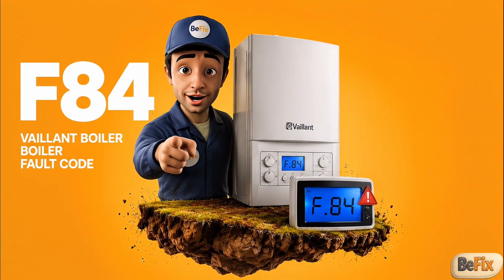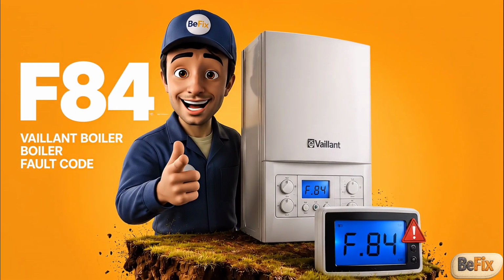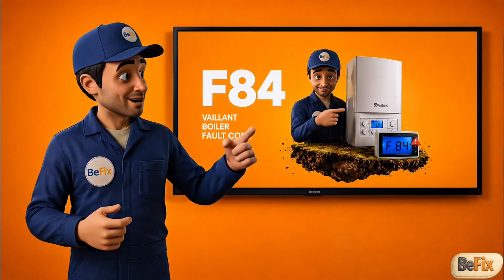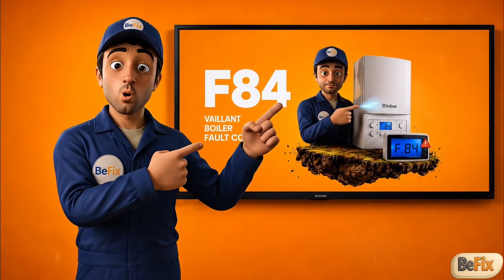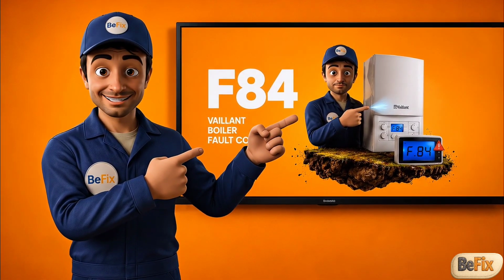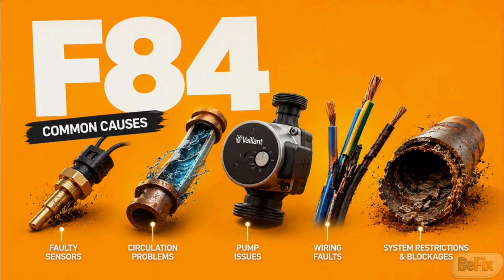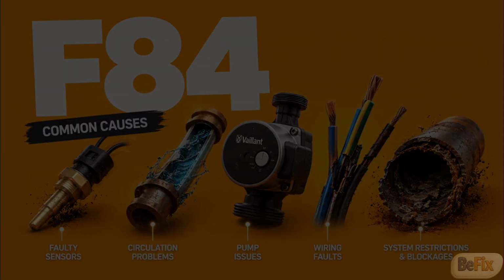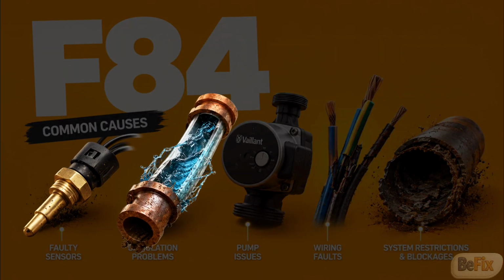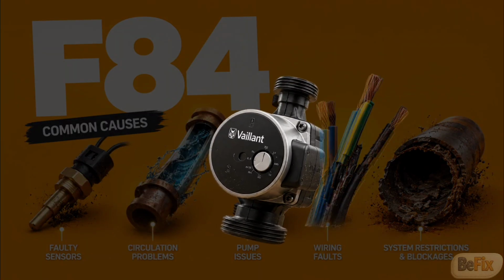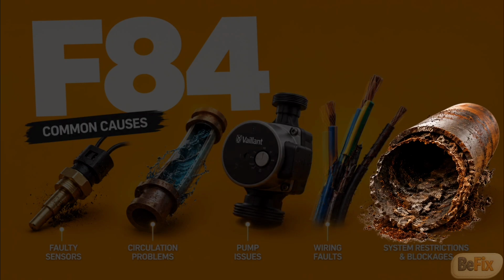If your Vaillant boiler is displaying an F.84 fault code, it means the boiler has detected an issue with the flow and return temperature readings. While that may sound complicated, the fault is commonly caused by faulty sensors, circulation problems, pump issues, wiring faults, or restrictions within the heating system.